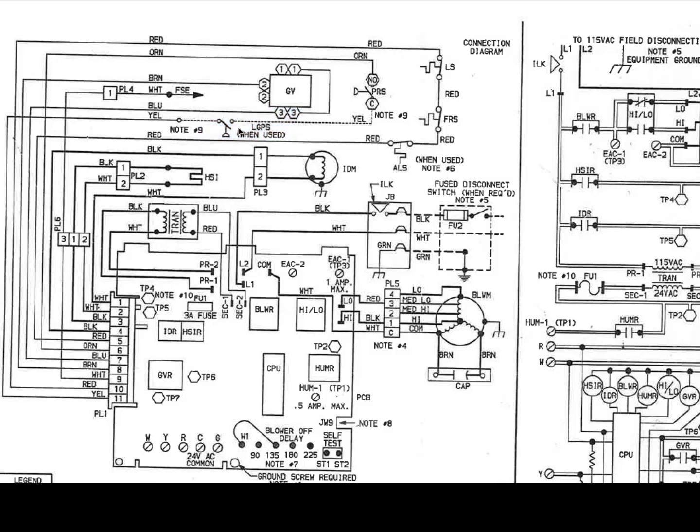So everything on this circuit is in the normal position right now because it's on a schematic or a diagram, and you should consider that to be de-energized, power's off, everything is in its normal state. So not tripped out on alarm, not locked out on some weird thing. The normal state is the system can run, but it's not running, power's off, and it's in its normal state.